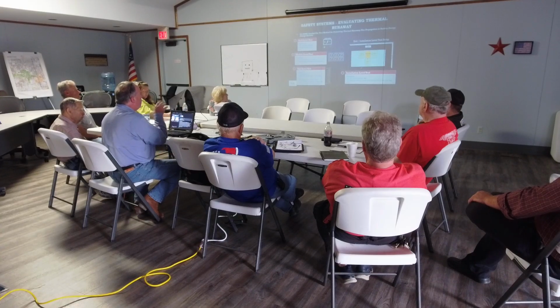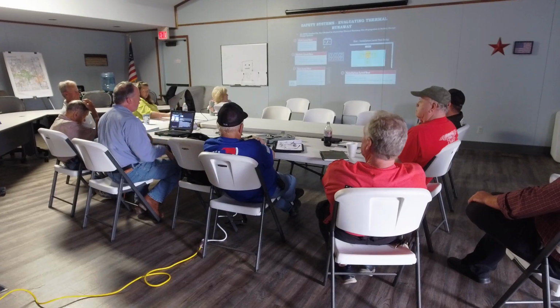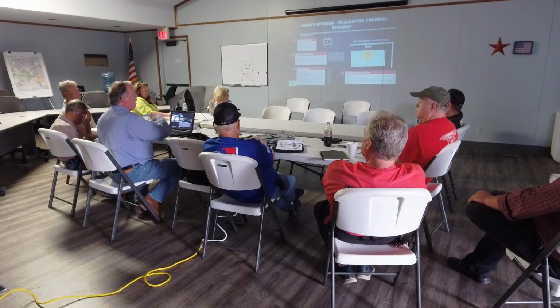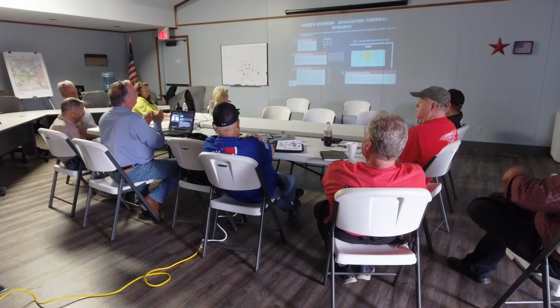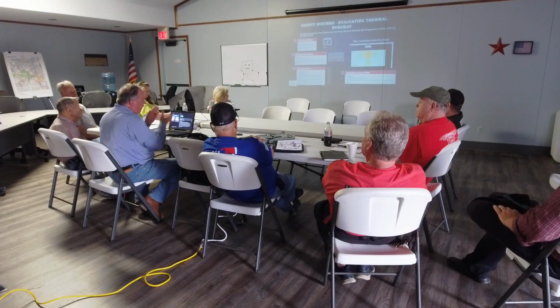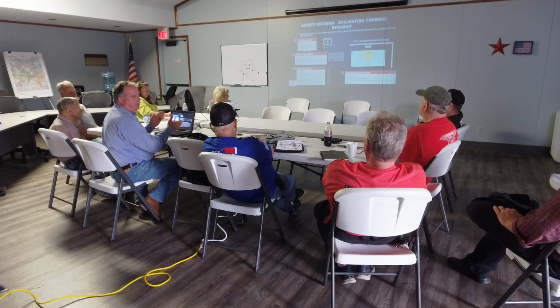From there, they'll do what's called a unit level test. They have a battery rack in their container, and they'll initiate again in one cell, then watch how that propagates through the rack, if it does. Most importantly, they're looking to see that it can't go from one rack to the next rack inside the container.